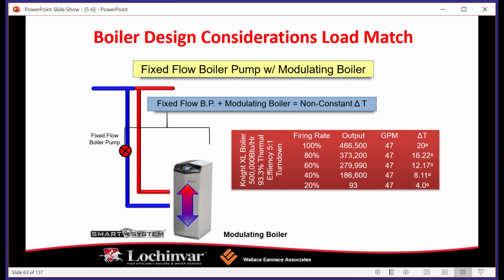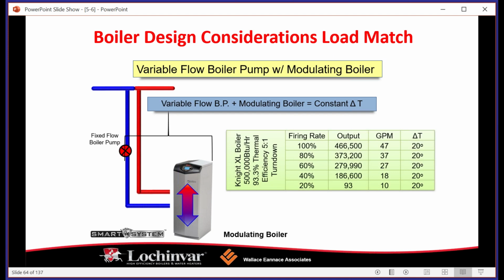So using this example, fixed flow, you're going to see that the GPM stays the same, but the delta is going to be significantly impacted by the boiler's flow through it. By using a variable flow boiler pump and a modulating boiler, we're able to maintain that delta T by varying the gallons per minute of flow through the heat exchanger to match the output firing rate. Okay, so again, on the boilers, you're going to have a pump that's provided with the boiler. For our purposes here, every time we quote you a boiler, we're going to recommend a pump that's going to go with it. It's going to be a variable speed pump that's going to allow those two pieces of equipment to work together to optimize your efficiency and to make sure that your equipment runs the way that we need it to.